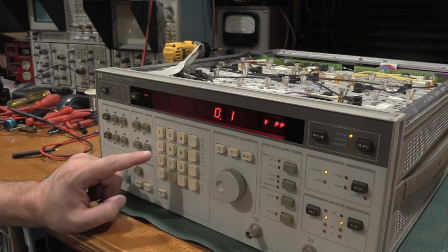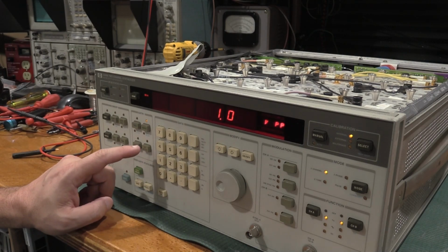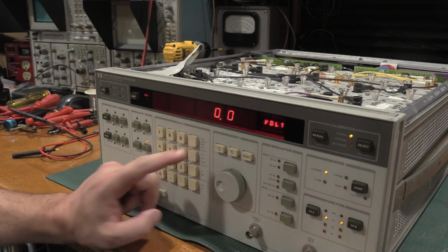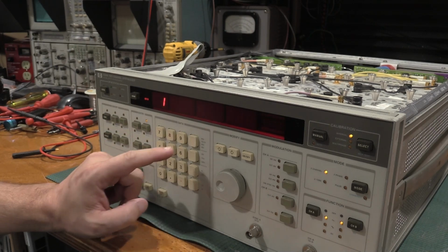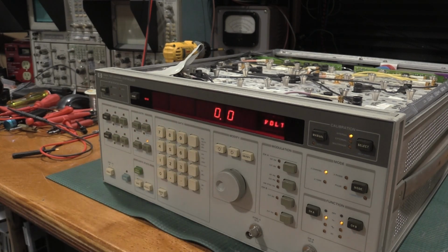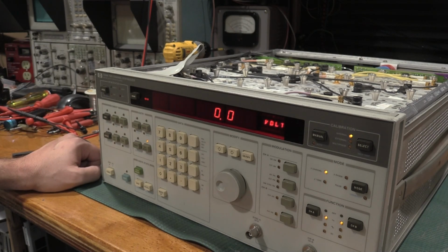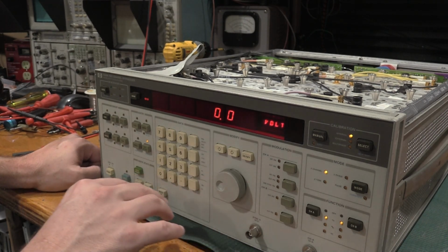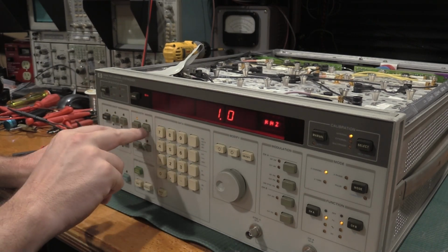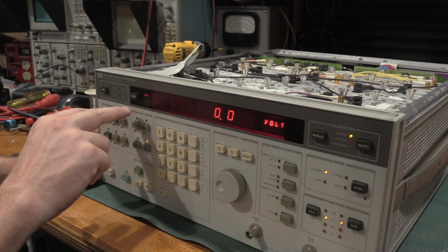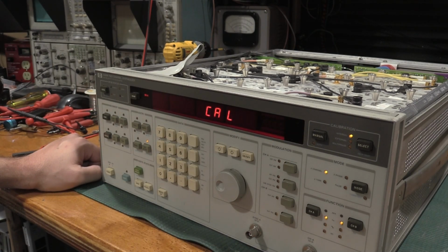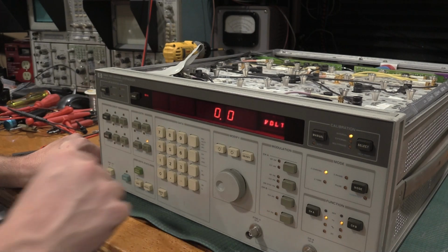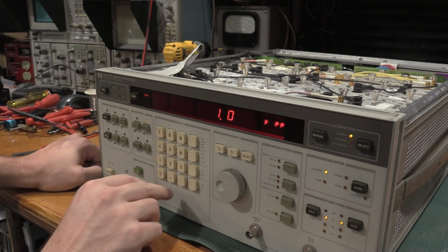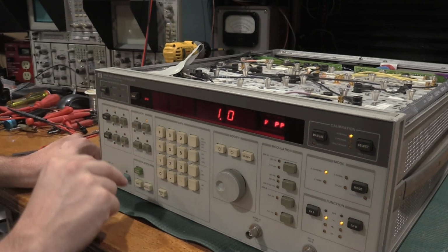So we'll set it to 1 volt amplitude, DC offset of 0 volts. Channel B, 1 volt amplitude, DC offset of 0. Now this was not calibrating prior - anything more than about a volt of offset and it would 193 all the time. 1 kilohertz, 1 volt, no DC offset, no phase shift. We got a 193. Let's add some voltage.